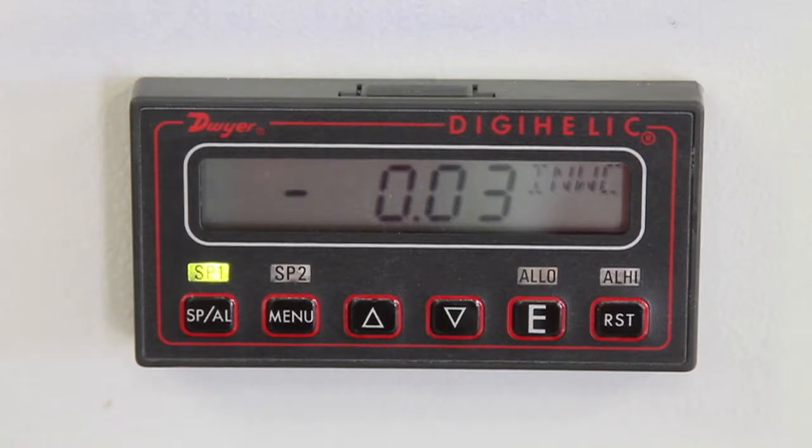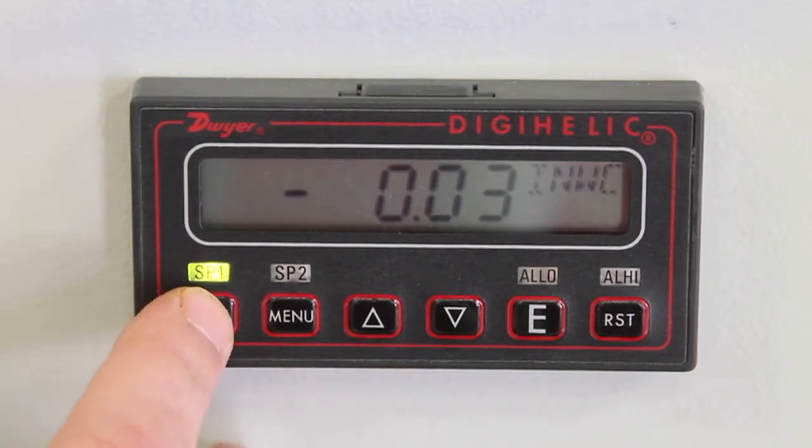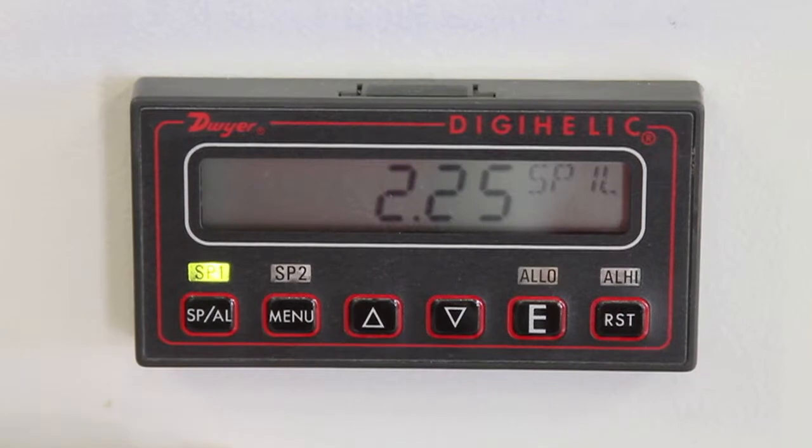Our first step is to review the high, low, and alarm set points and make sure they are to factory set points. To do so, we'll push the SPAL button. It will bring up 2.25 SP1L. This varies by model. Check your owner's manual to see what yours should be.